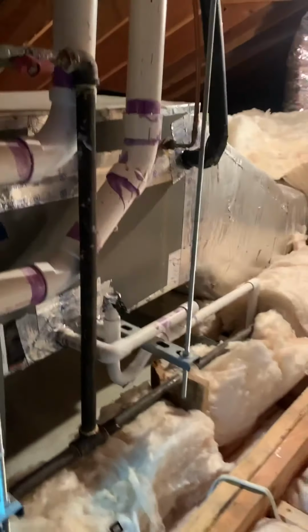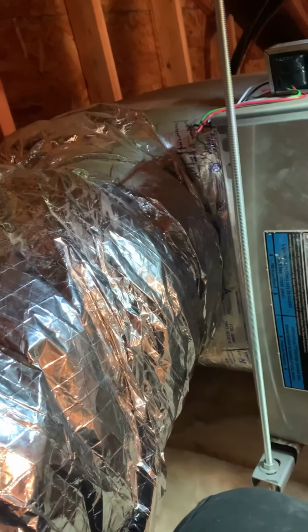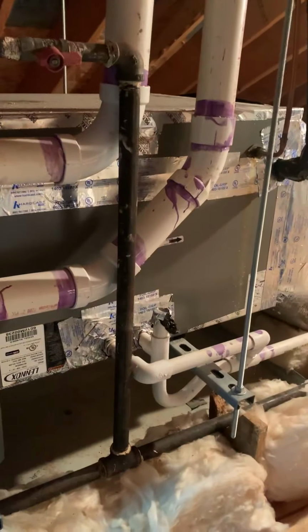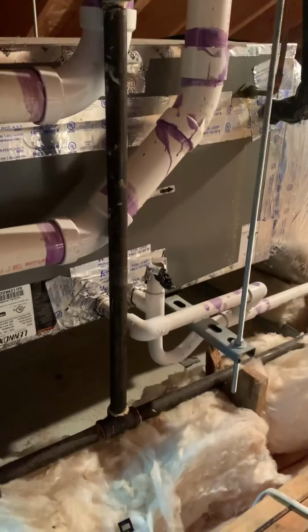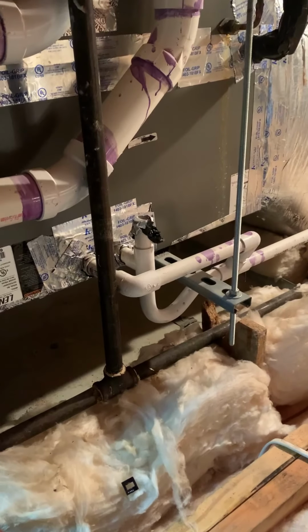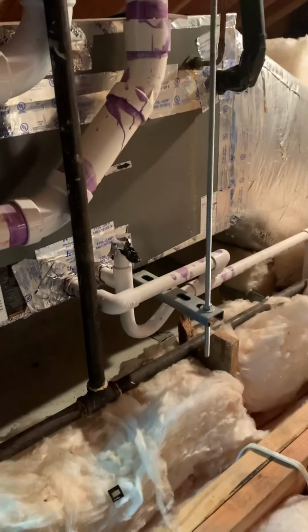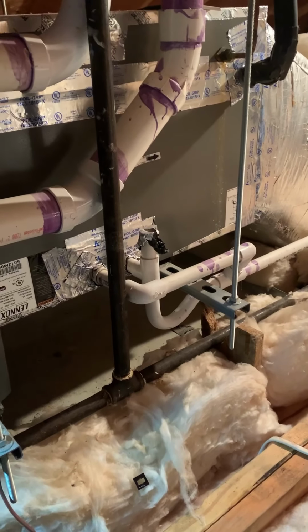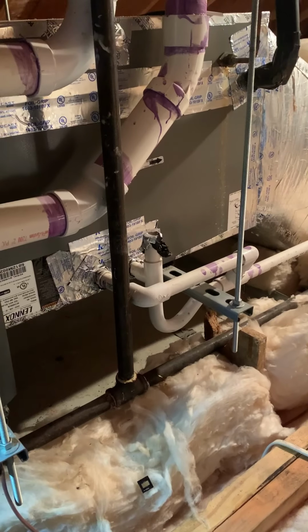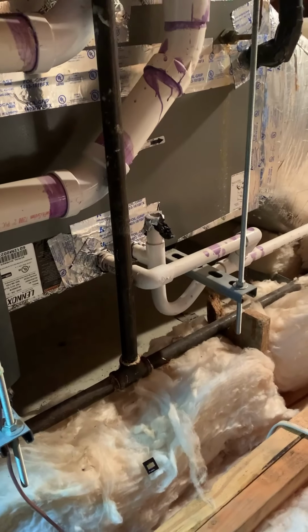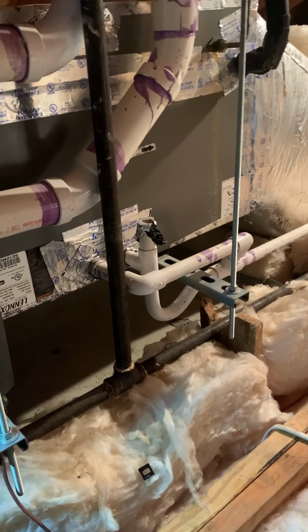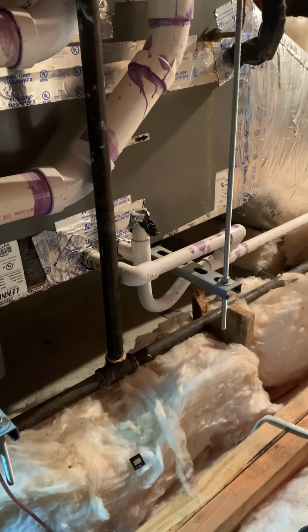And you know what? Just to give you guys a little bit of a sidebar. Okay, this is the return, right? So that's sucking air in, going through the coil, going through the blower assembly, through the heating assembly, and goes to the coil. Whenever you have a coil on the positive side pressure, you don't need a trap, because that air is going to blow that water out of that coil. Sometimes they say a trap is not good to have, but whatever. That could just be a regular straight pipe.